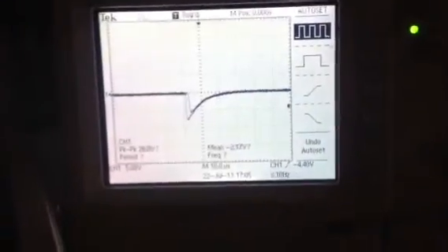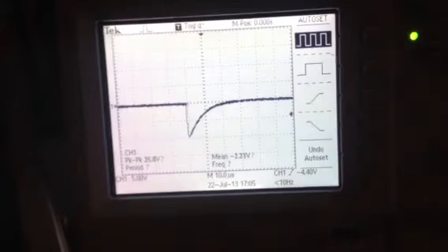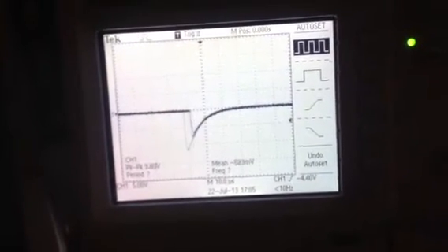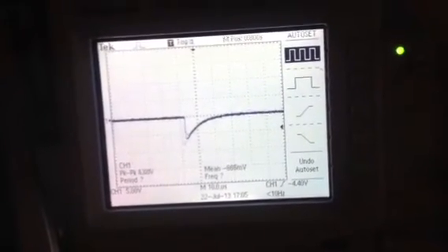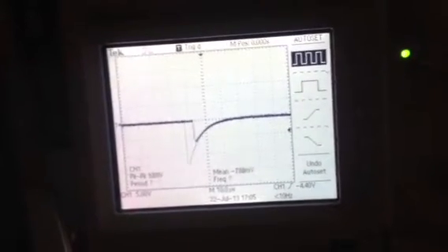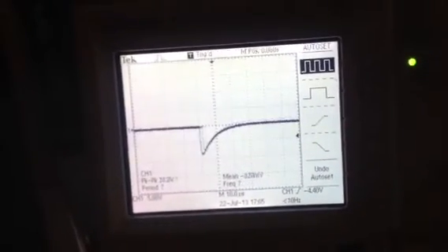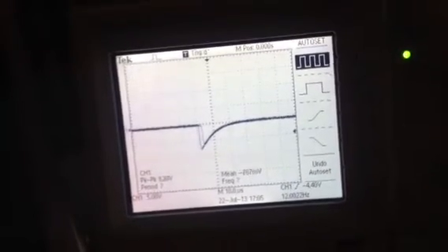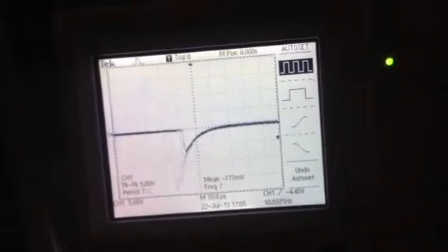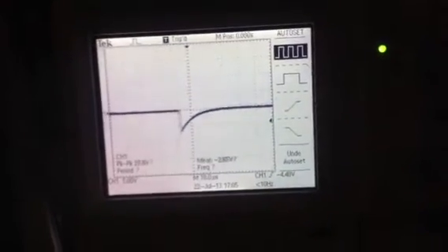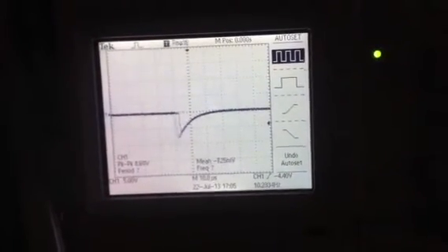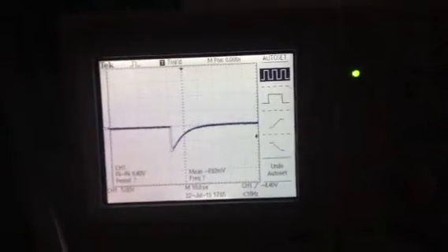So we're getting some pulses from the scintillation detector, probably just from background radiation or cosmic rays. Pretty fast pulses there, so about on the order of 10 microseconds. But there's a distinct train of pulses there coming in pretty regularly with differing amplitudes, which is what you'd expect for different photon energies. That's not a bad pulse amplitude actually. That's straight off the photomultiplier tube with no active amplification or anything.